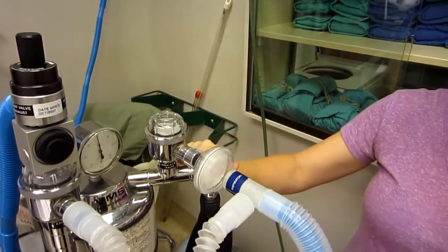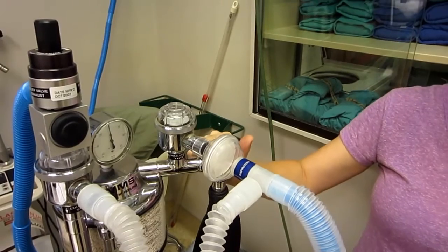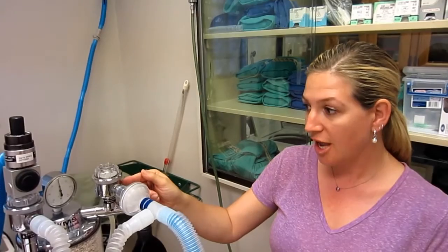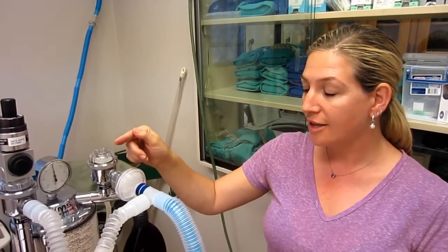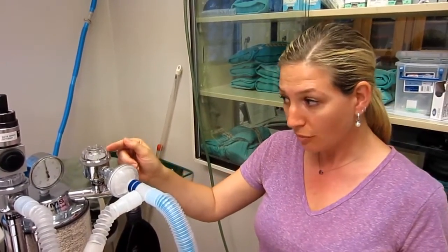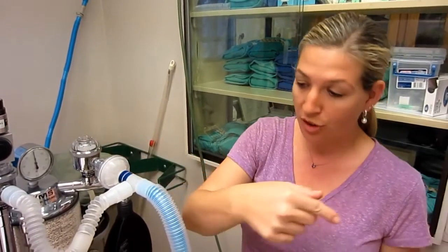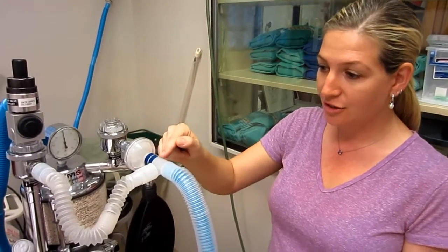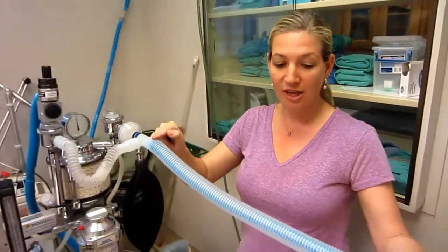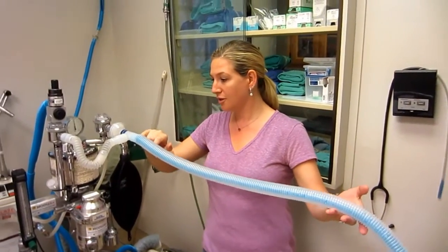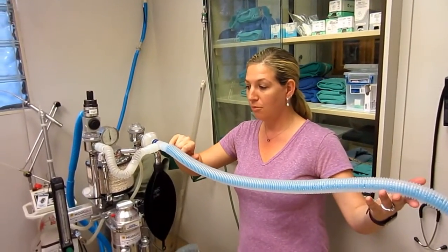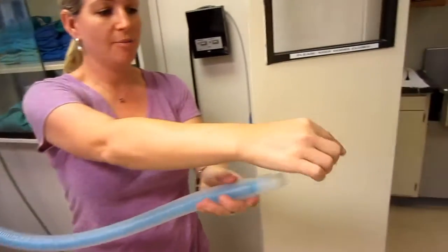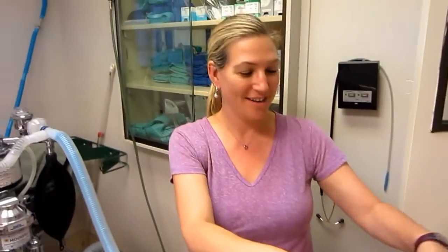Now, the inhalation valve is also known as the unidirectional inhalation valve. And just as its name suggests, it will only allow the isoflurane and oxygen to go one direction, which is towards the patient. So it comes up through here and into the patient. Now, this is the inhalation tube. It's a little hard to see, but it's the corrugated blue tube inside. So it would go down, and we'll say our patient's out here. We'll pretend it's on a table.